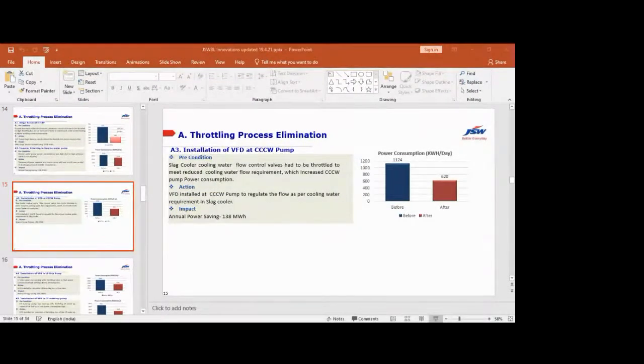Installation of VFD at the CCCW pump. Same as the earlier slides, we had to do some throttling on the cooling water. We provided the VFD, so the throttling was removed, and we are getting the advantage of removing throttling losses. Earlier the power consumption was 1124 kilowatt. After the VFD, it is 620 kilowatt, and the annual power saving is 138 megawatt hour.